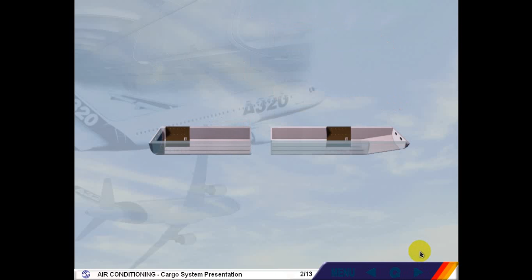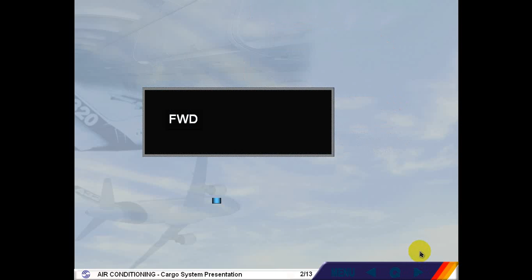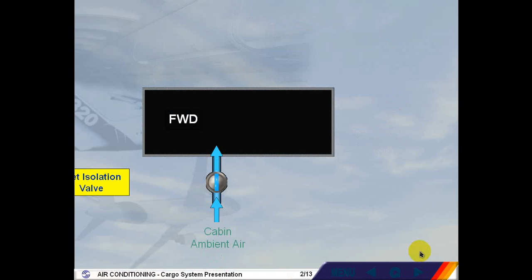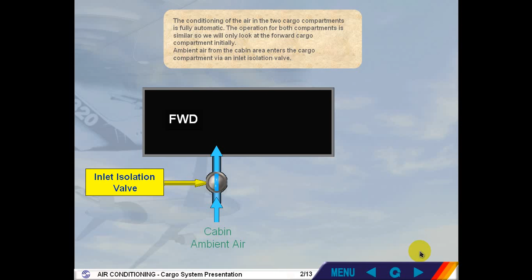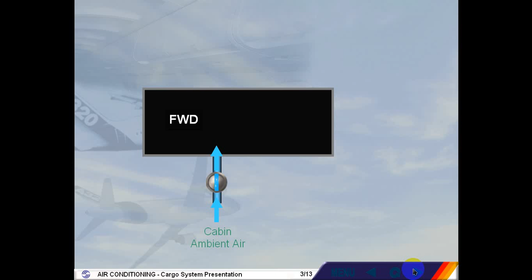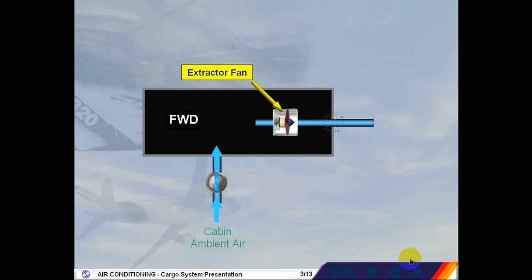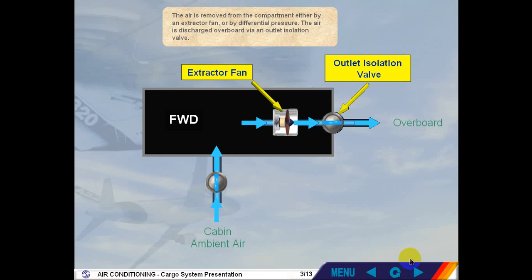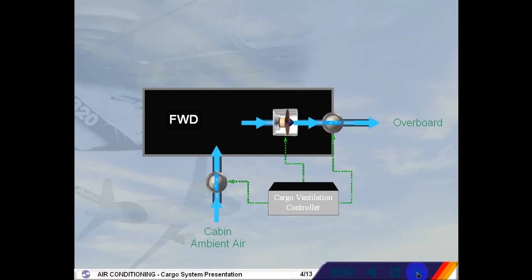The conditioning of the air in the two cargo compartments is fully automatic. The operation for both compartments is similar, so we will only look at the forward cargo compartment initially. Ambient air from the cabin area enters the cargo compartment via an inlet isolation valve. The air is removed from the compartment either by an extractor fan or by differential pressure. The air is discharged overboard via an outlet isolation valve. The operation of the two isolation valves and the extraction fan is controlled automatically by a cargo ventilation controller.